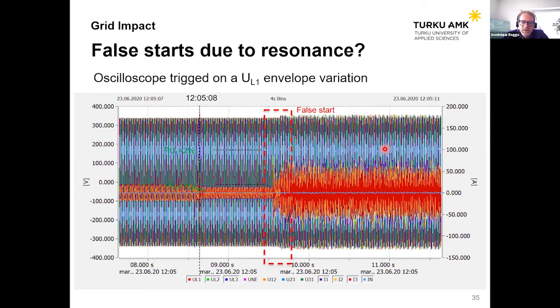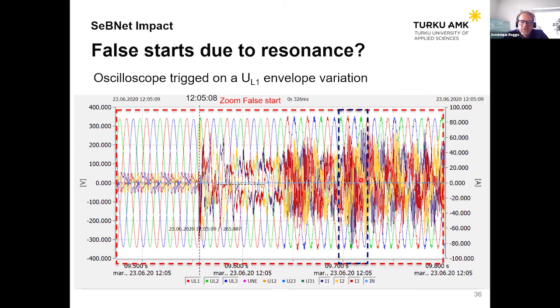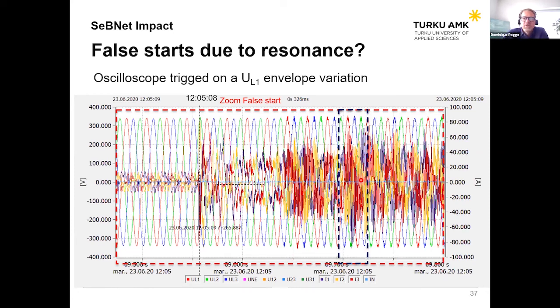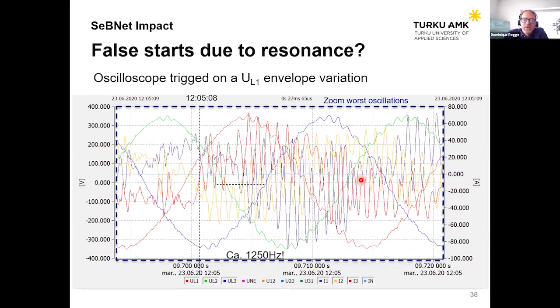Zooming into this area when the problem starts, we can see a lot of disturbances, a lot of oscillations. This is really not normal behavior, or let's say not optimal. Zooming in deeper, we can see this oscillation, and indeed the current, with very high values on the order of 50 amps, is oscillating by more than 1 kilohertz. So there's a very unstable behavior at this point.